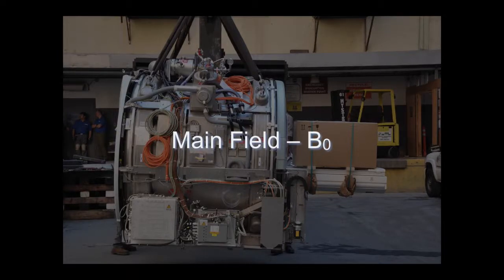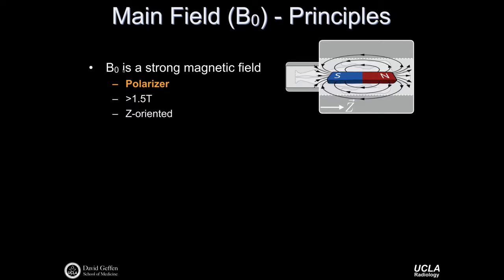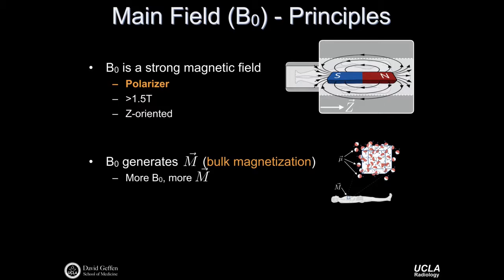Graphically, we can depict the main magnetic field as a north-south facing magnet oriented along the z-axis of the scanner, generally the foot-to-head direction. The B0 field serves to polarize the underlying magnetic spins such that we get a coherent population predominantly in the spin-up position relative to spin-down. The magnetic field strength is typically greater than 1.5 Tesla. The more B0, or the stronger the B0 field, the more bulk magnetization we have available for forming images, and the stronger the signals will be for higher quality images.